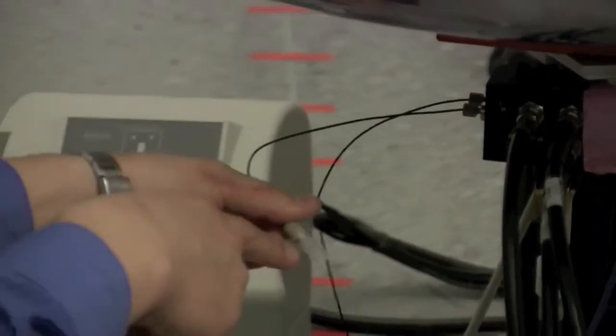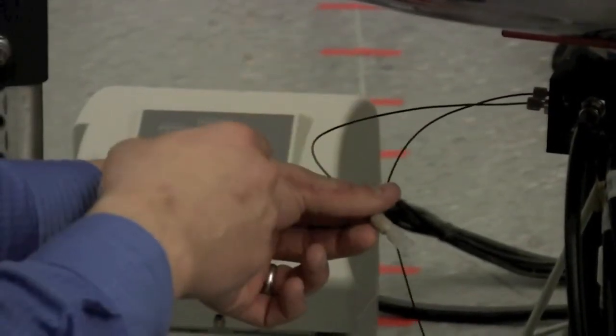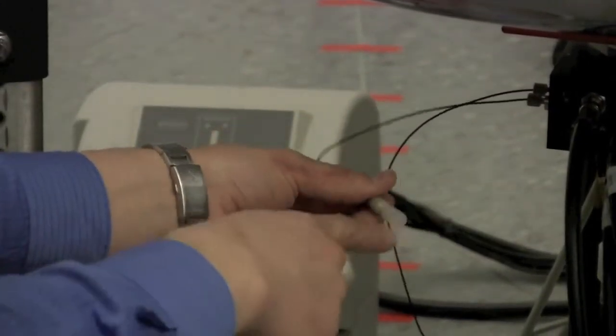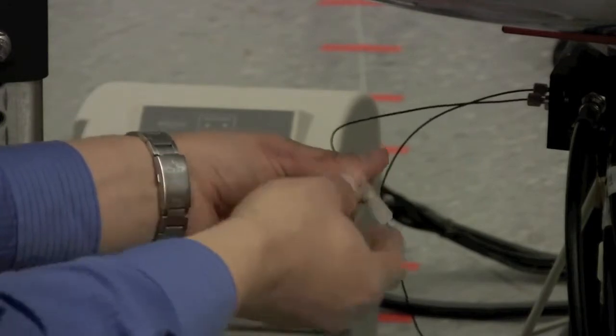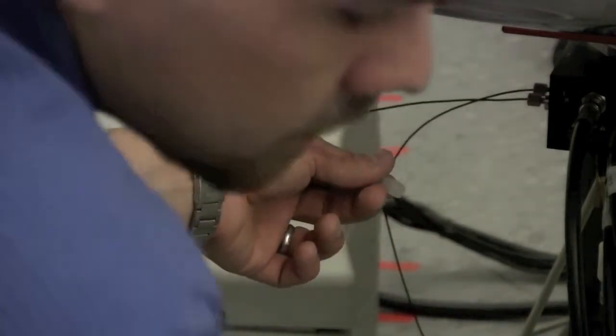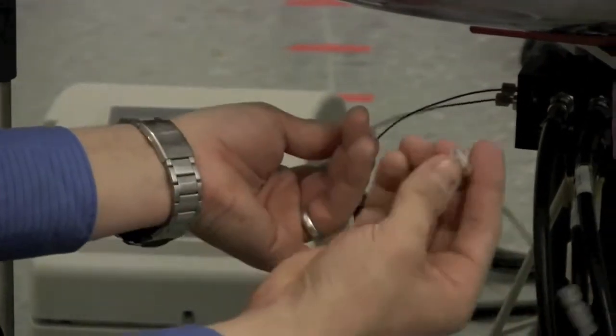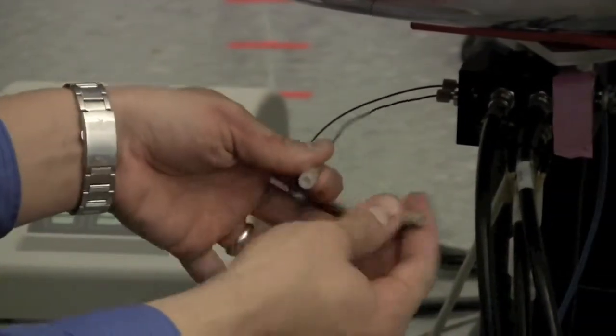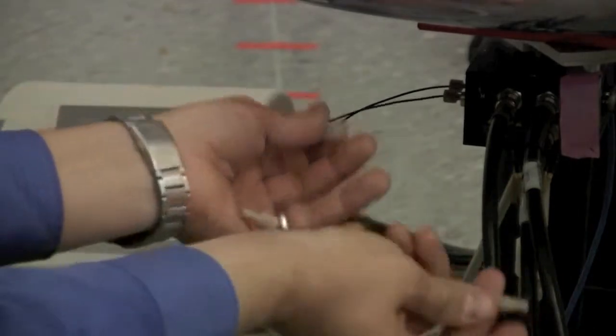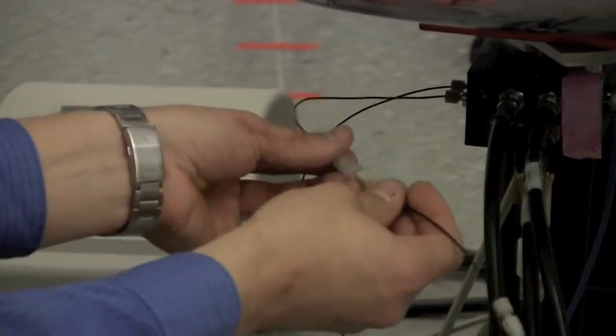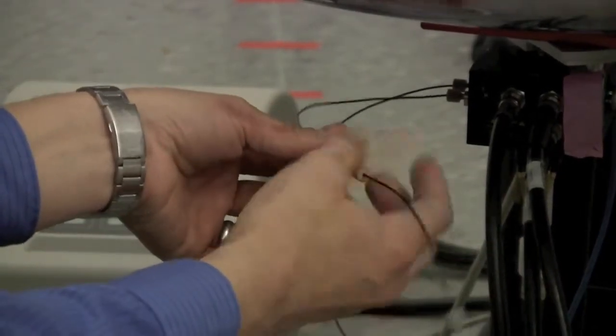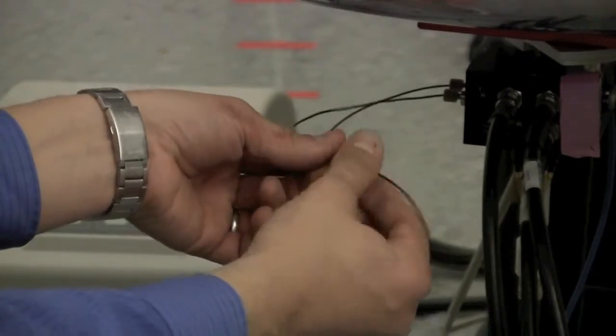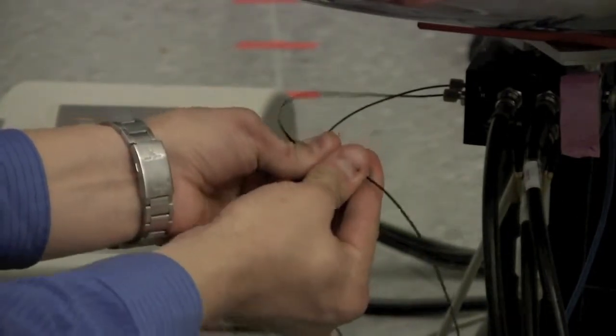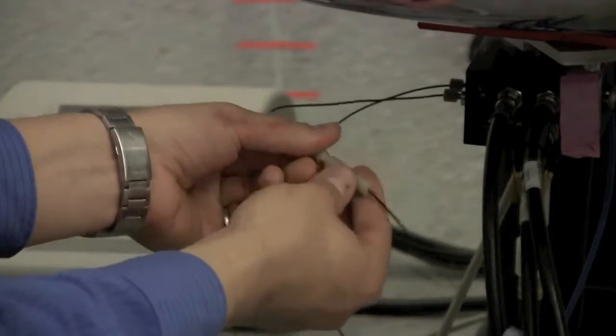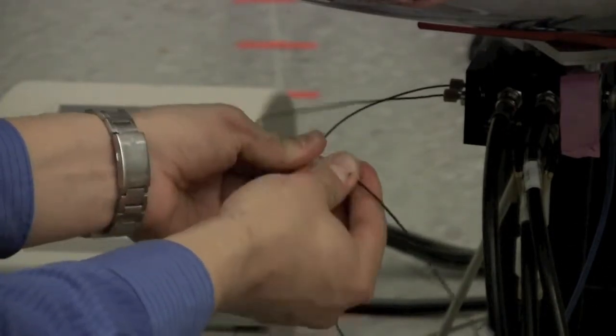The advantage of this filter, in addition to allowing us to make sure that the probe doesn't get clogged, is it allows us to put a few different fittings on the end here. So the first fitting we're going to use is this one that goes from a flat connection to a luer lock connection, like on a syringe. And this is what we're going to use to push the solvent out of the probe with air. So I'm going to tighten this down. All of these connections should be finger tight. Don't tighten them as tight as you possibly can, but they need to be tight enough that they're not going to leak.